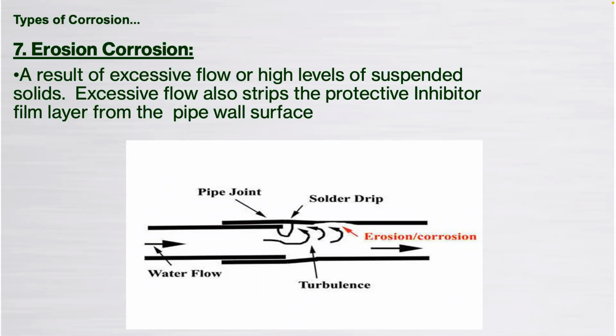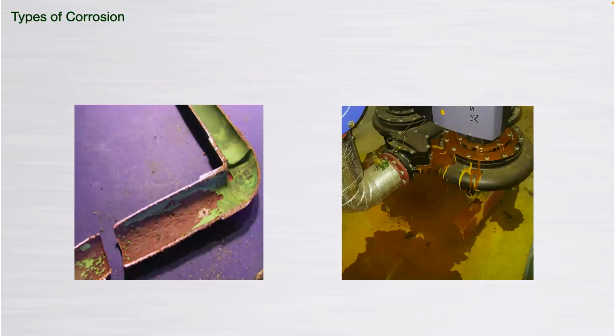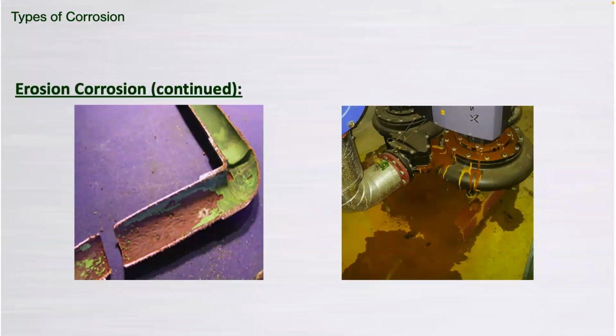Either is really erosive, too much velocity, or too much in terms of suspended solids, like shot blasting down the pipework. So again, good filtration is required, and at the same time, making sure that we aren't over-egging our flow rates, making sure our flow rate design around our system is accurate enough and within ASHRAE guidelines to support velocities through the system. Not too low on velocity to let things settle out, but certainly not too fast either.